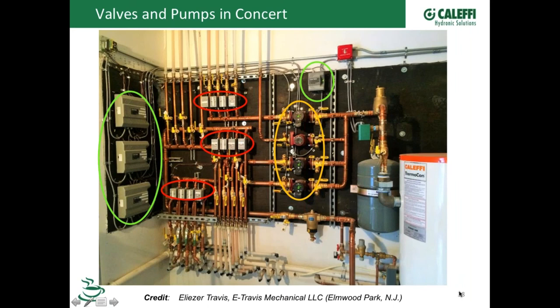Yeah, I really wouldn't recommend putting the pump for the indirect on the other side of this buffer, because in a lot of cases, I would assume a lot of these zones are going to be low temp zones, whether it be radiant or panel radiators or whatever. So that buffer tank is going to be 130, 140 degrees tops. And then all of a sudden you need your indirect to kick on. Well, obviously you don't want to heat that whole buffer tank up to 180, because then you're going to have too hot of water going out to your zones after that indirect priority is over.